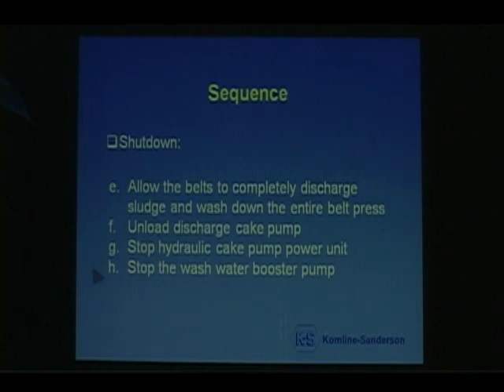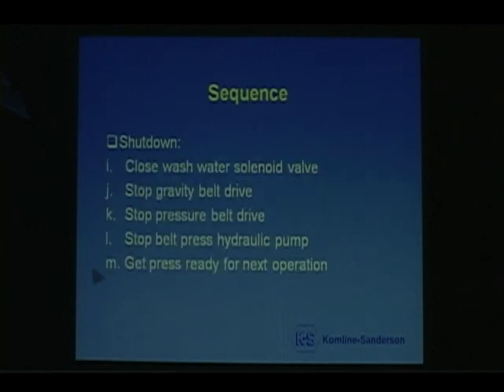Then you can stop the hydraulic cake pump power unit, stop the wash water booster pump, close the wash water solenoid valve, stop the gravity belt drive, stop the pressure belt drive, stop the belt press hydraulic power unit, then get the press ready for the next operation.